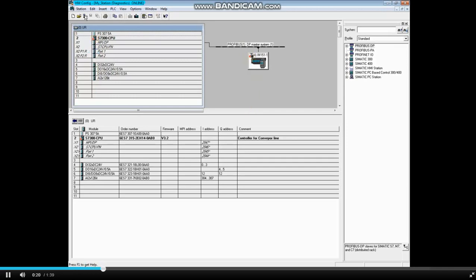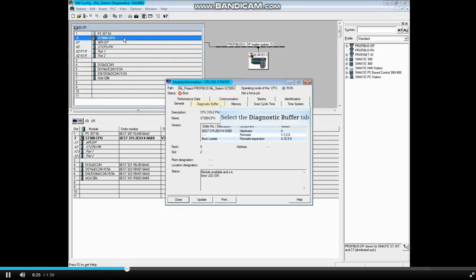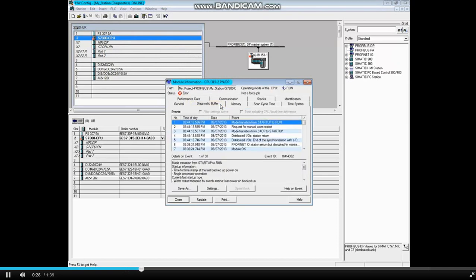While online, double-click the CPU to open the Module Information tool. Click on the Diagnostic Buffer tab. There is no relevant information here, so let's go to the Station Diagnostics.